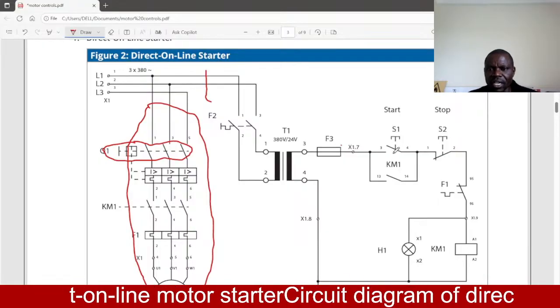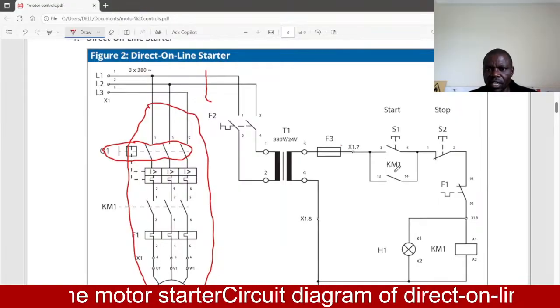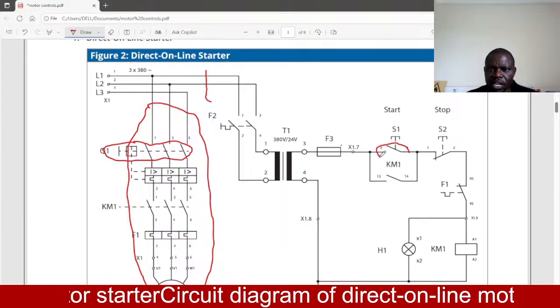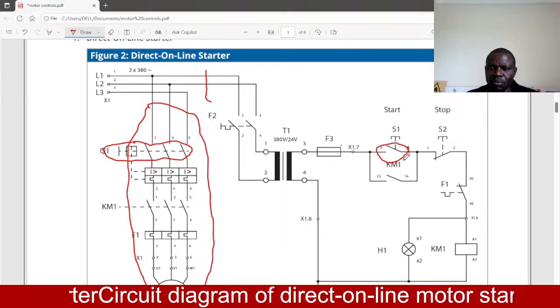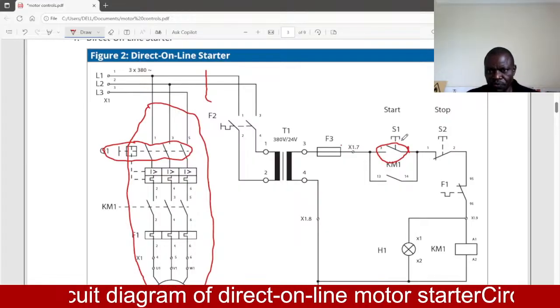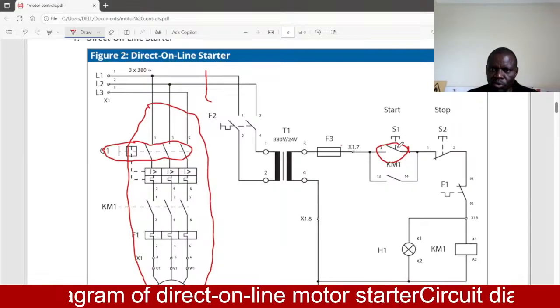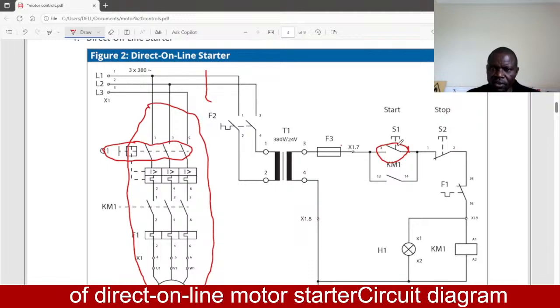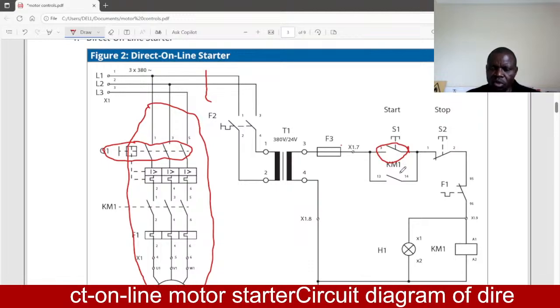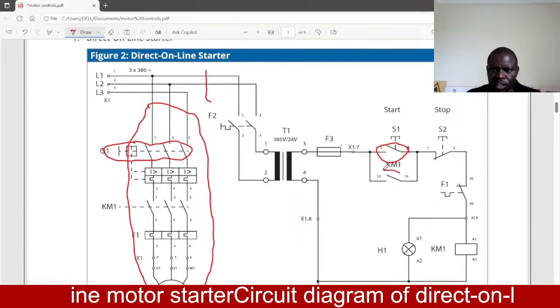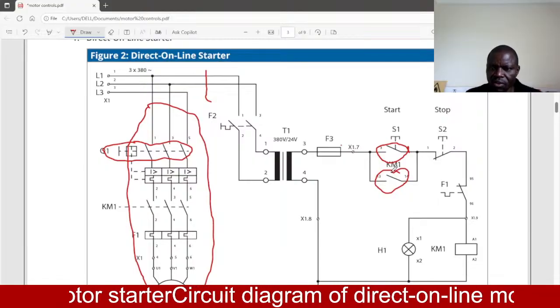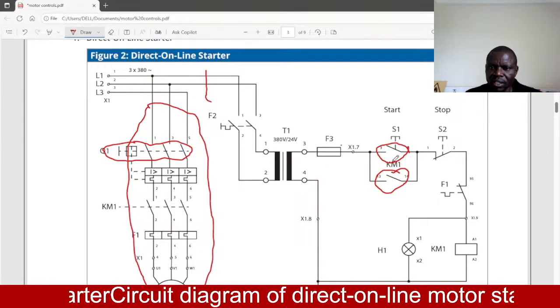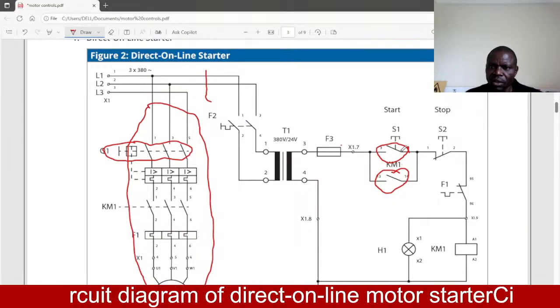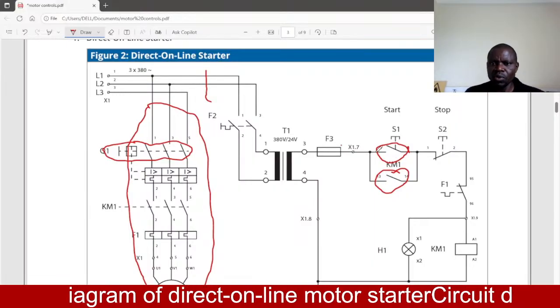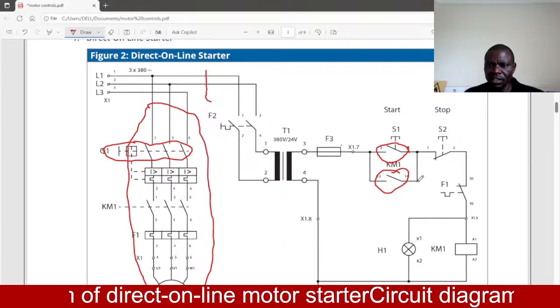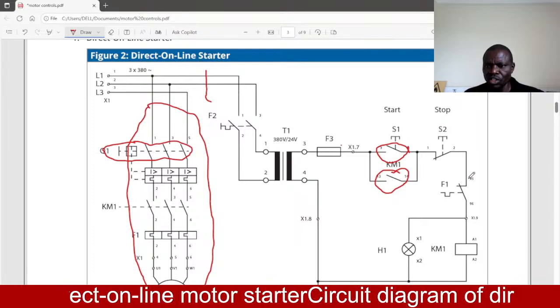Now we have these two contacts named 3, 4 and 13, 14. 3, 4 here is a contact that is making what we call the start push button. This symbol here shows a push button, and when you press it, it is spring loaded; it will release after removing your finger. Then we have KM1, which is marked 13, 14. This contact here is what we call an auxiliary contact that latches the KM1 after the switch 1 here has been released, because it will open. So we want a continuous flow of power running from this point to this point and continuously to the coil.